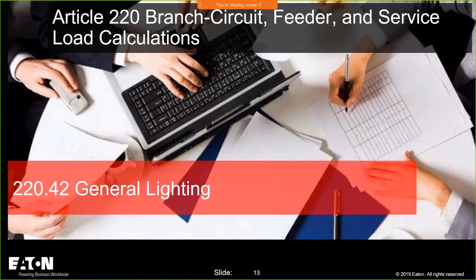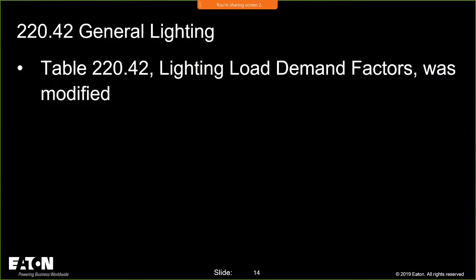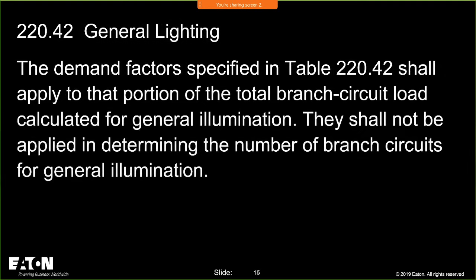So that's what we did. Keep in mind, all of those VA per square foot values changed, and what drove that was the lighting and LEDs and all that good stuff. Now because we made that change in 220.12 and reduced those multipliers, we had to come over here in 220.42 and change the lighting load demand factors, because we were taking too much of a bite out of the loads. And it made a lot of us on panel 2 a little bit concerned.